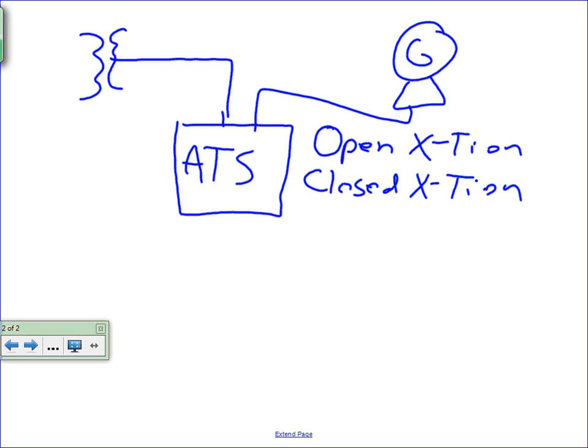So obviously it's pretty self-explanatory. In an open transition, if you lose your utility, you go to generator power. Obviously that's open anyway because you already lost the power. The transfer switch will send a signal to the generator. The generator will start up. Once the generator is up to speed and frequency, the transfer switch will close to the generator power and provide power. Now it's when the utility comes back that this difference comes in, right?